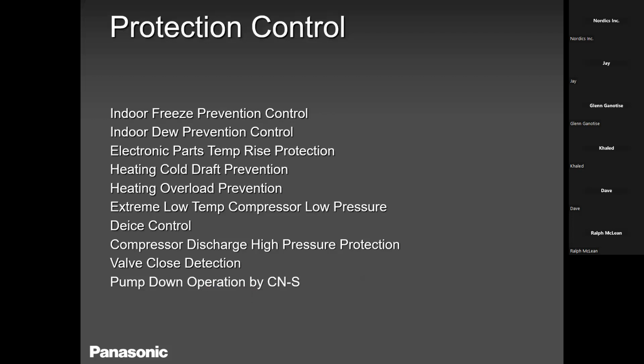Correct. Stepper motor, yeah. EEV is something similar to a stepper motor. So with our units, we always protect our coils. We always protect our indoor coils from busting. And we have something called H99, which is a protection error, not a malfunction. So please keep that in mind. Our units are pretty strong, pretty robust. Indoor freeze protection is constantly monitoring the temperature of the coil. So when the temperature of the coil goes below 0 degrees, the unit is going to shut off, and it will come back on again. And if it happens 4 times in 1 hour, the unit is going to shut off, lock out, and you will get an H99 error.